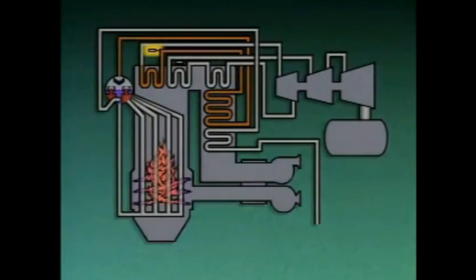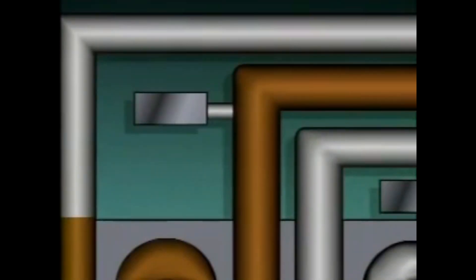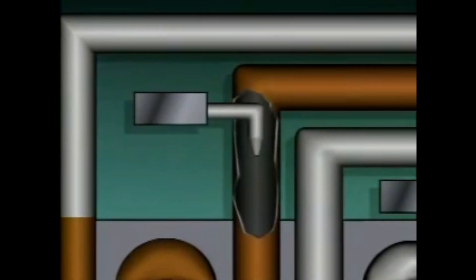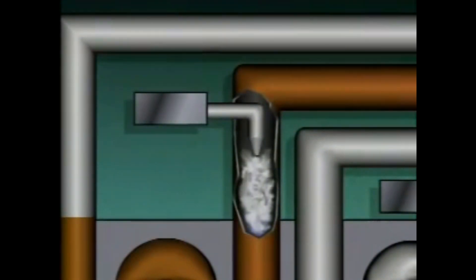This boiler has an attemperator, or desuperheater, located between the primary and secondary superheaters. The desuperheater keeps the steam from becoming so hot that it damages the superheater tubes. If the steam gets too hot, the desuperheater sprays water into the steam flow. This water immediately flashes to steam and mixes with the steam that is already there, resulting in a decrease in the temperature of the superheated steam.